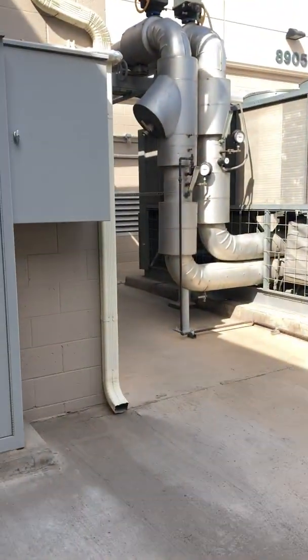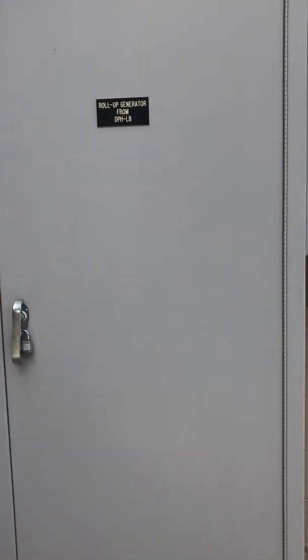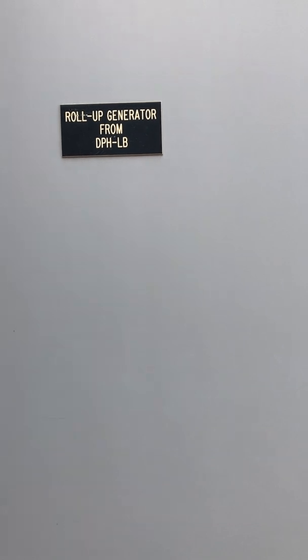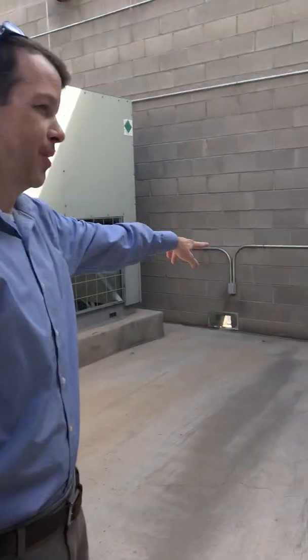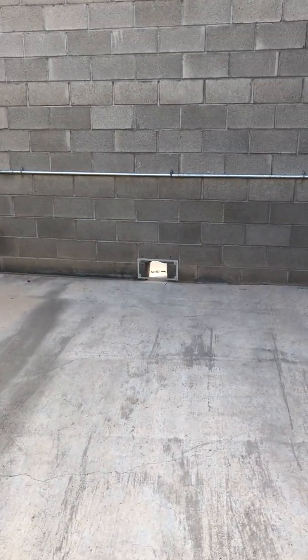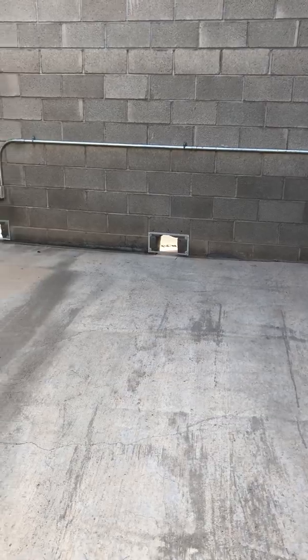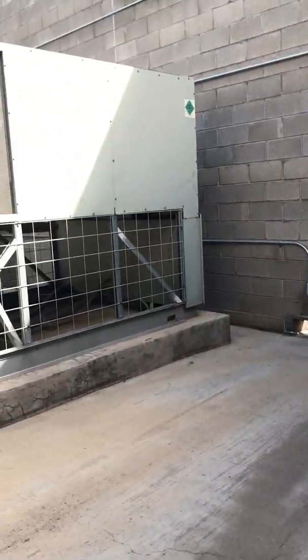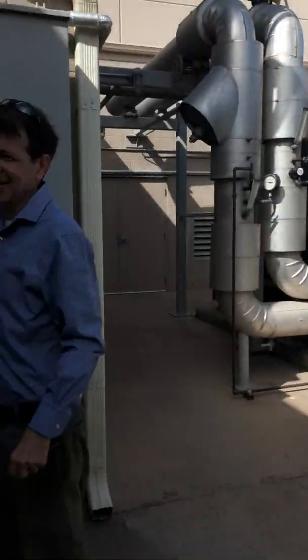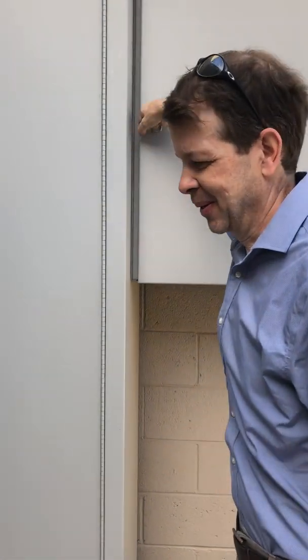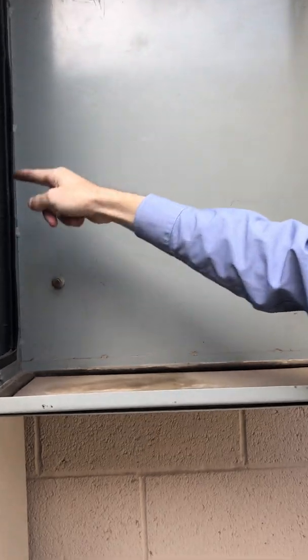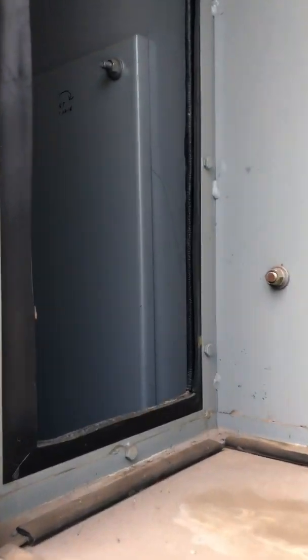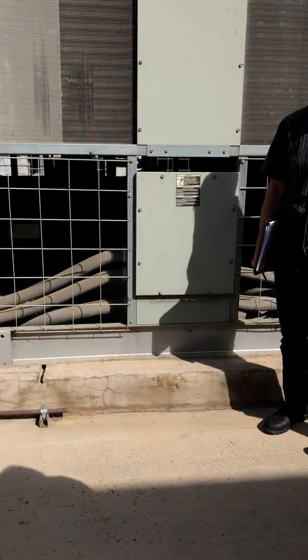To use the roll-up generator or the load bank, we're able to run the cables through the guarded access points. This is normally locked, but I've got it unlocked for the tour. The cables will come up through this rubber grommeted connection to land on the bar. I've got the phase rotation marked on there to attach properly.